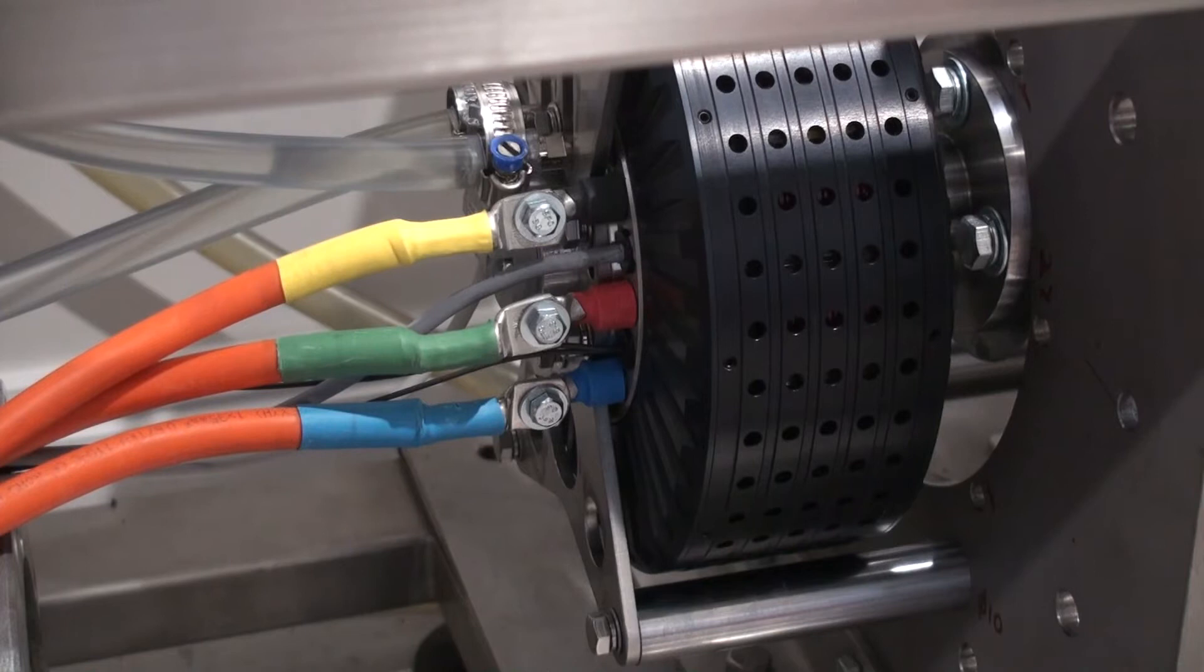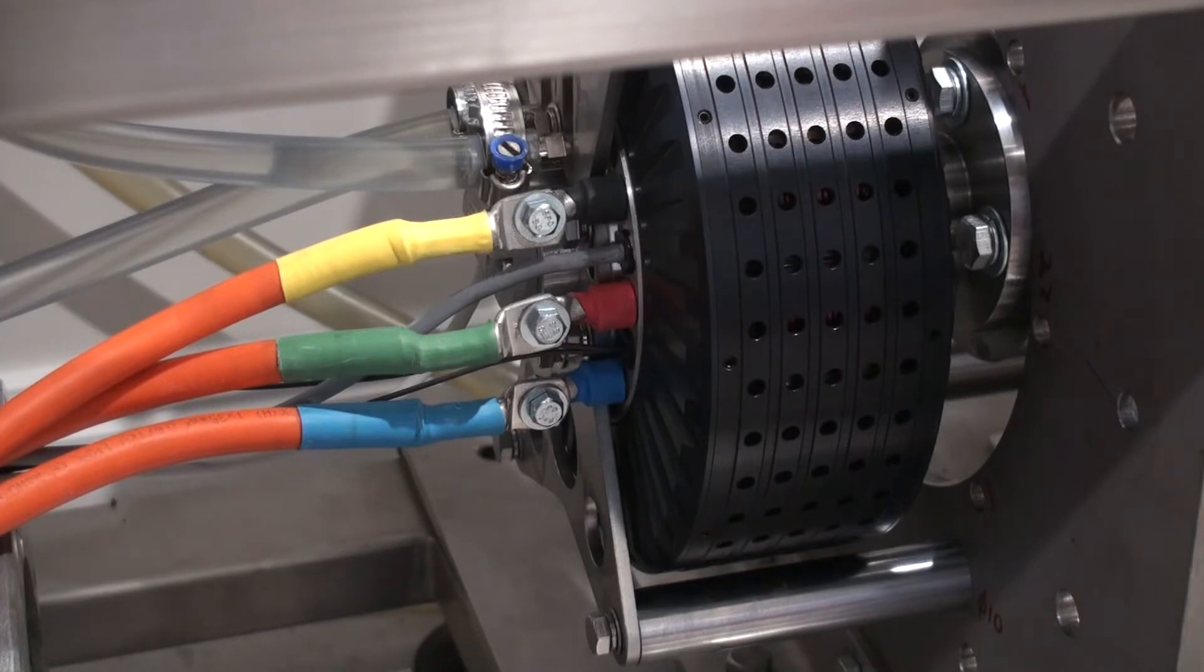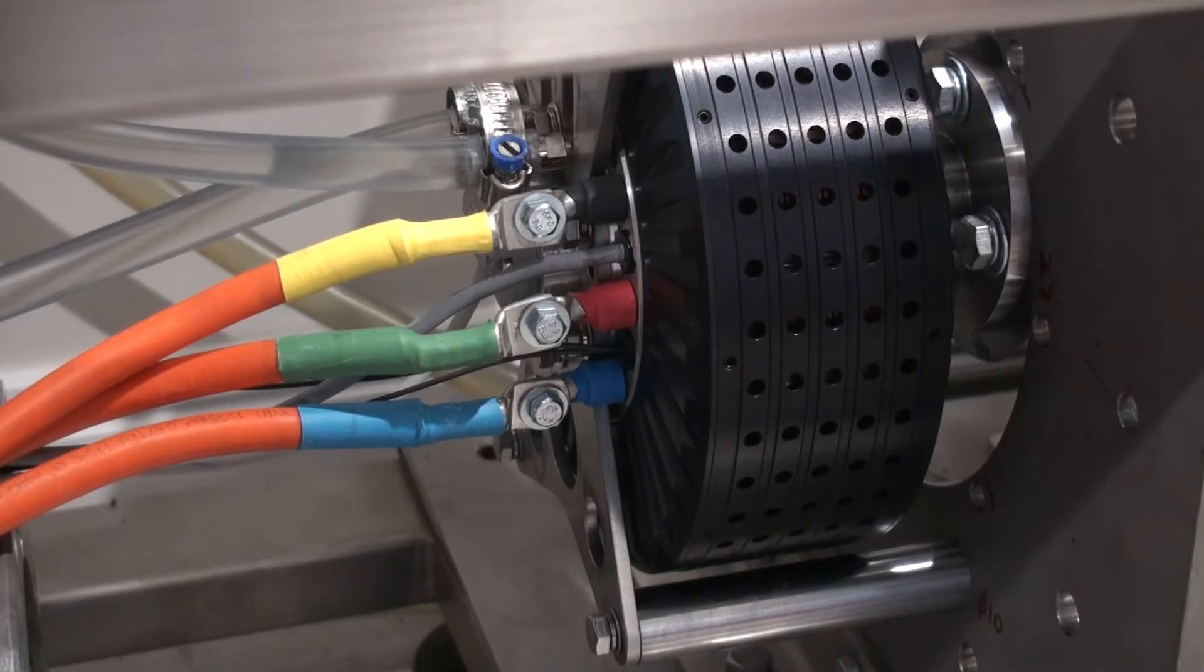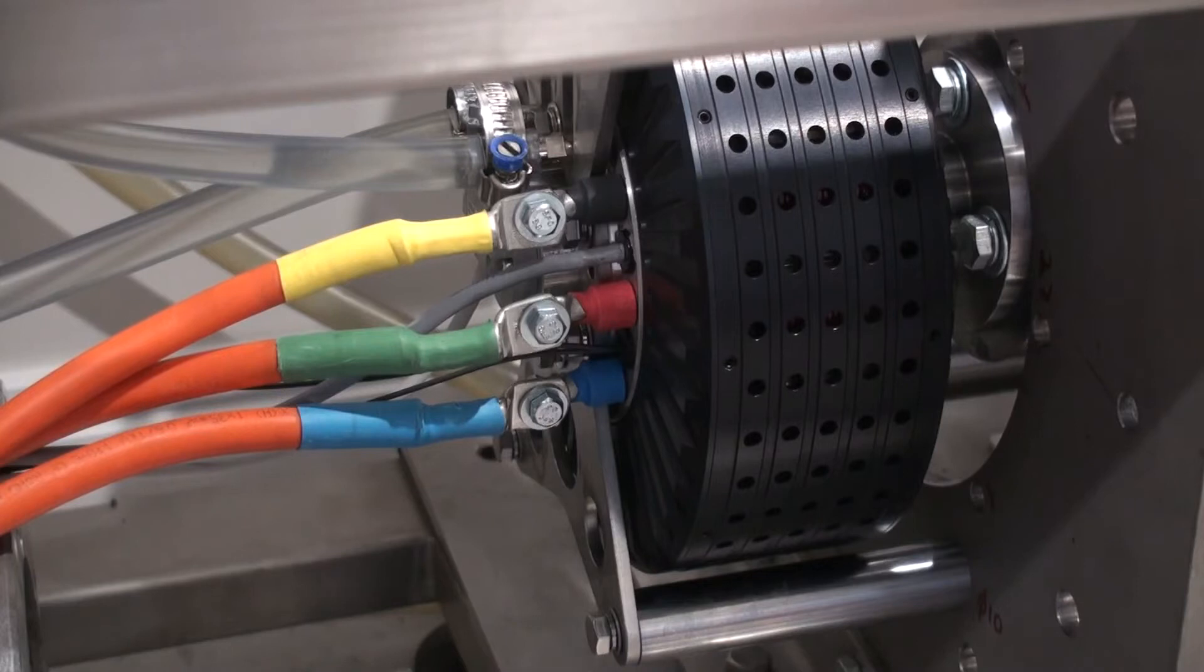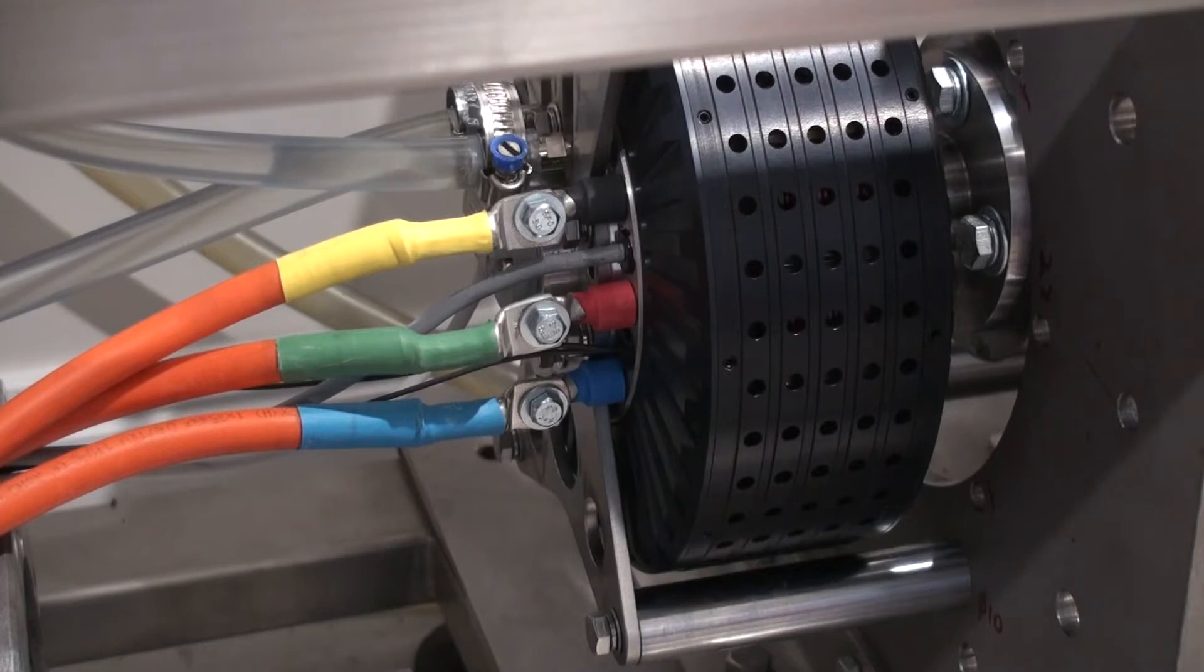Now this motor also comes in three different voltage options and has three different maximum currents. The low voltage option has a maximum current of 900 amps. The medium voltage version which this one is has a maximum current of 340 amps and the high voltage version has a maximum current of only 240 amps.